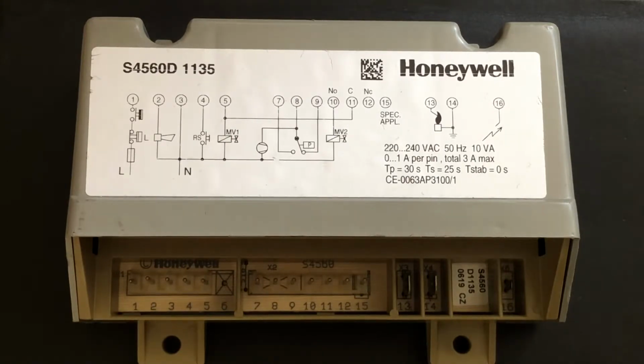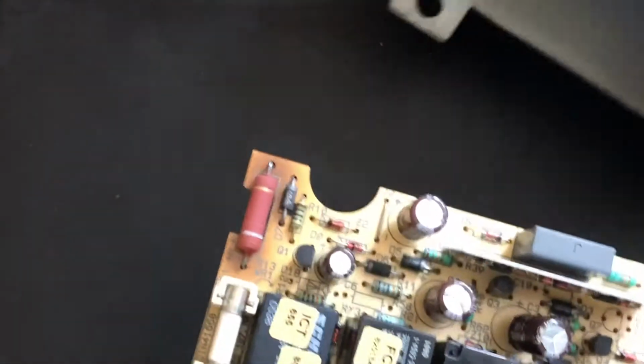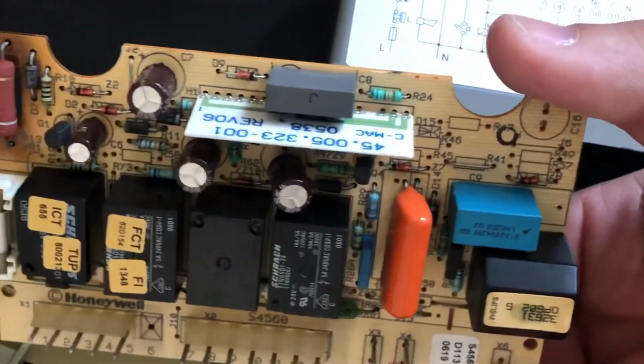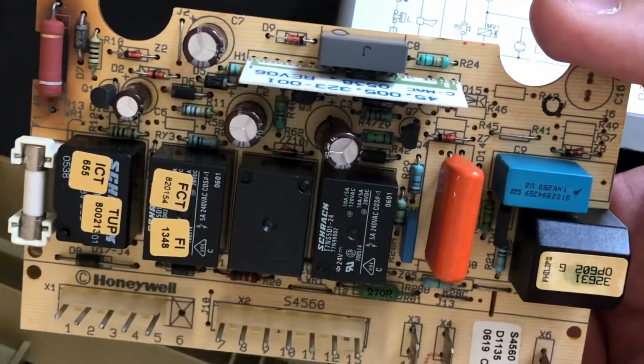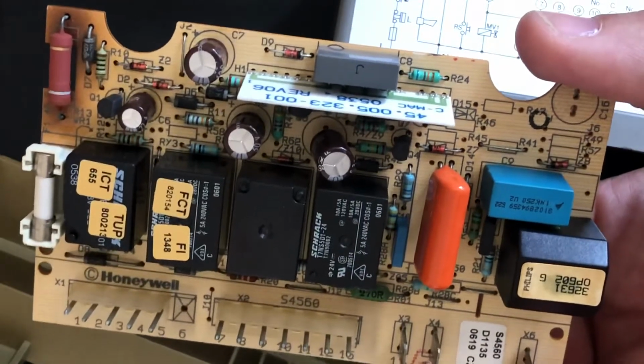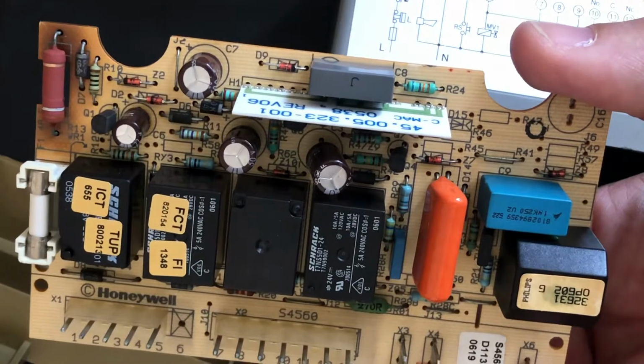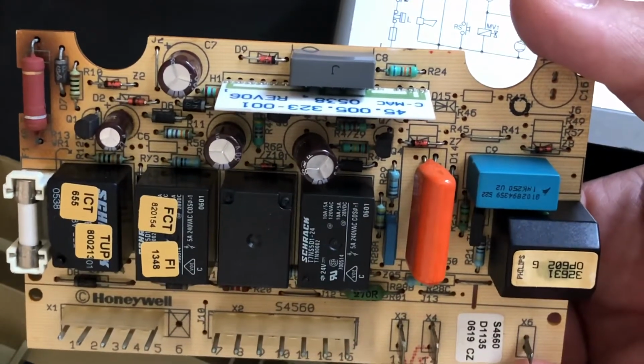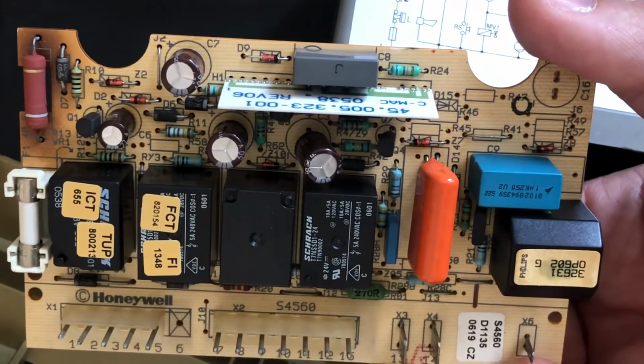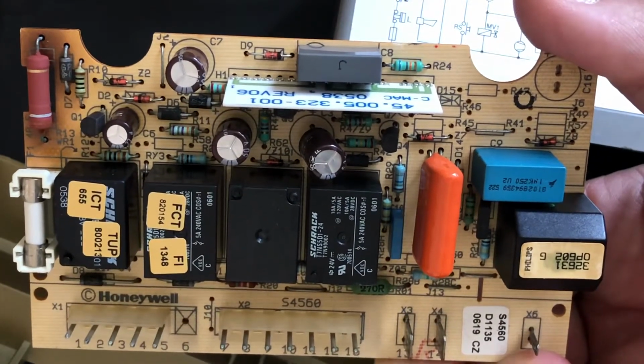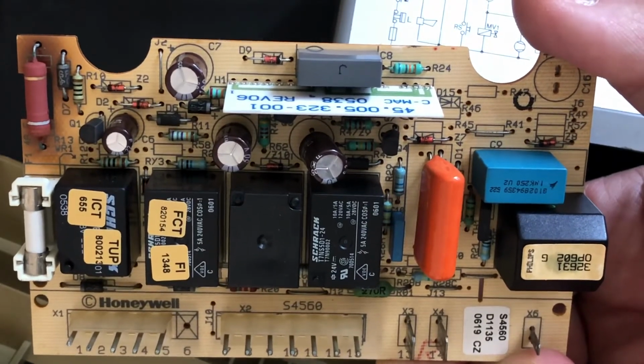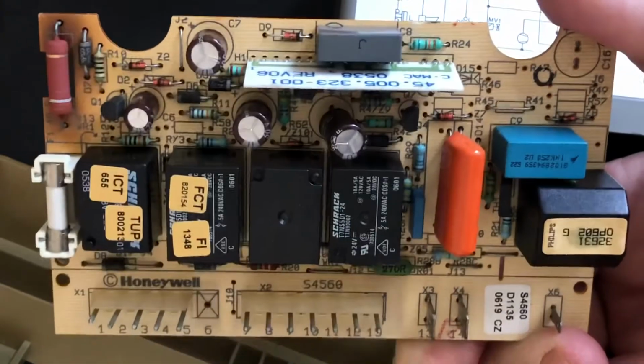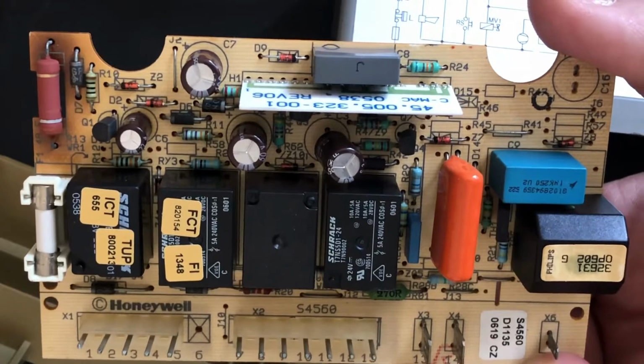If this system doesn't work, before you rush into spending a lot of money to buy a new one, I'm going to open this for you. It's enough to open this box, and inside you'll find an electronic circuit. This electronic circuit is not good to mess up with because there are a lot of safety features designed by the manufacturer, and if you interfere with the electronic parts, you can affect the safety of this burner controller. Without knowing, you can make a mistake and some glitches can happen inside. So the burner might run the gas valve without a flame because you can affect the ionization probe signal reading module, and that will be a very bad idea because you can happily die. I mean unhappily die, not happily die.